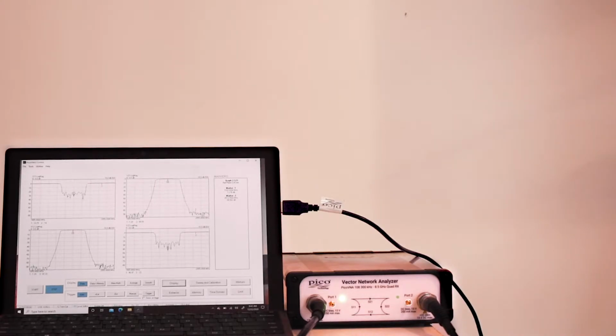This differs from the more comprehensive factory calibration performed on sensitive instruments such as the oscilloscope, spectrum analyzer, and VNA. Factory calibrations are typically done before the initial purchase and subsequently once a year or as required. They involve sending the instrument back to the manufacturer, where technicians open the enclosure, do whatever it takes, and certify that the equipment conforms to the original specifications.